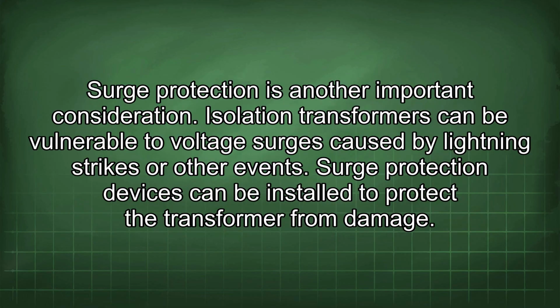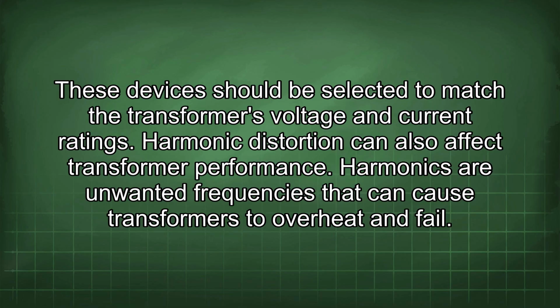Surge protection is another important consideration. Isolation transformers can be vulnerable to voltage surges caused by lightning strikes or other events. Surge protection devices can be installed to protect the transformer from damage. These devices should be selected to match the transformer's voltage and current ratings.